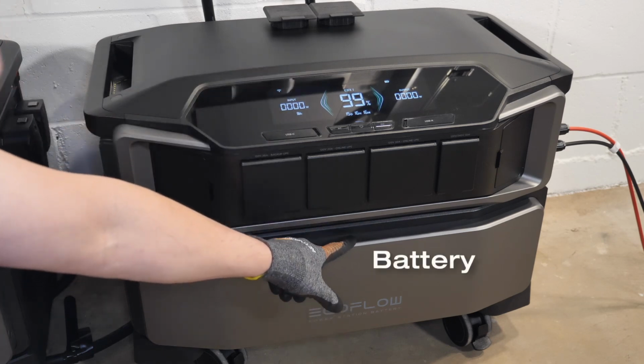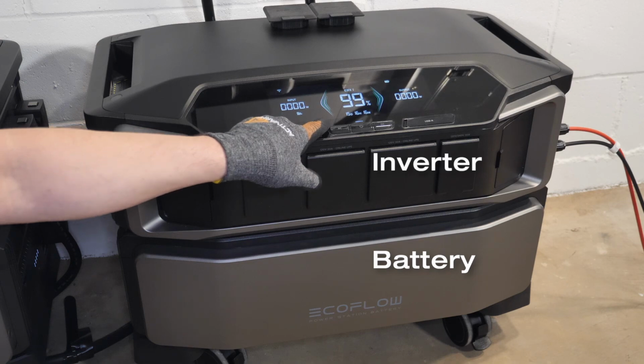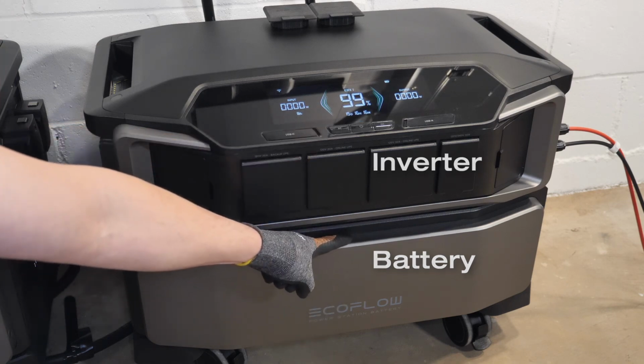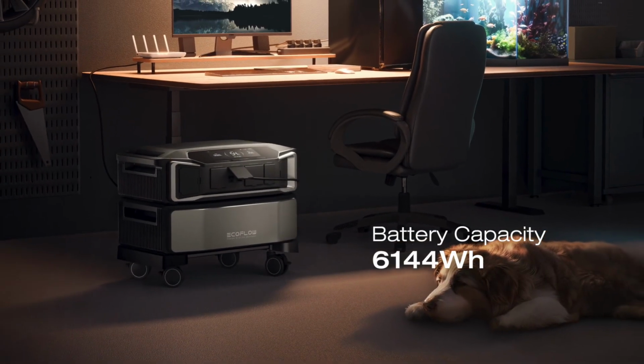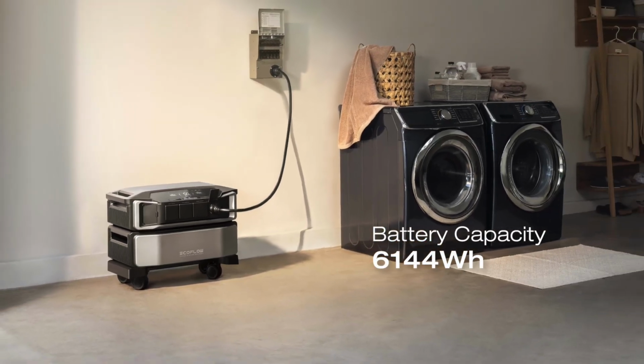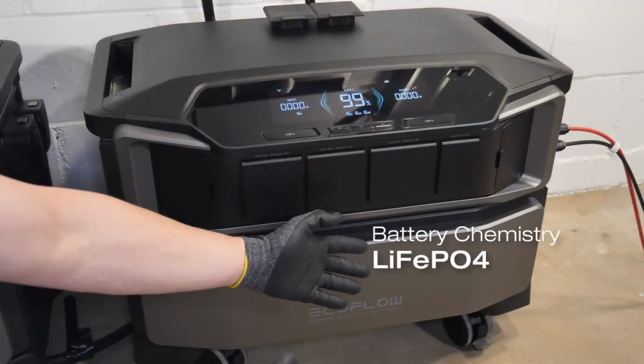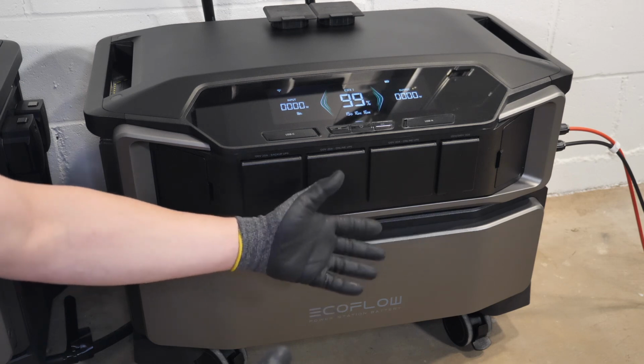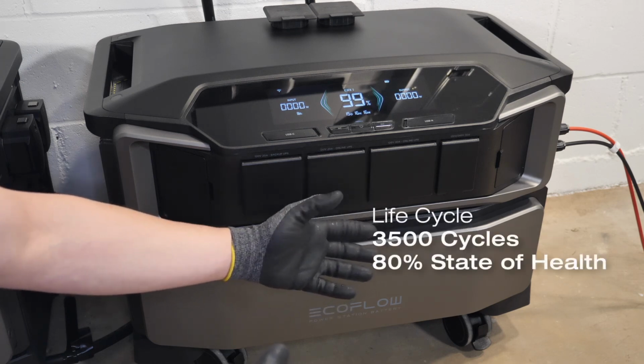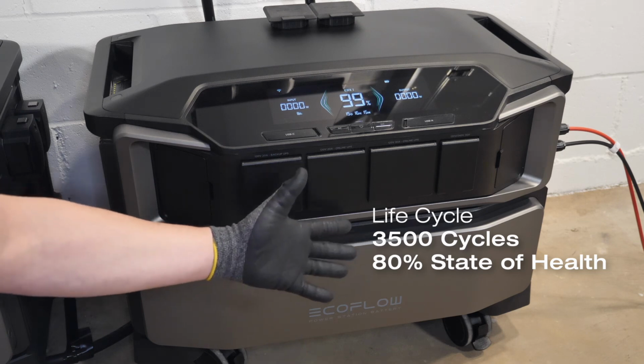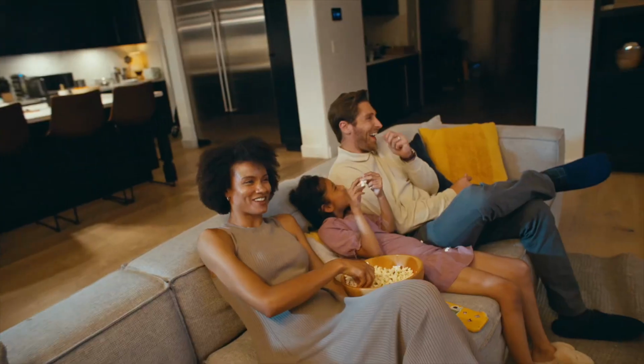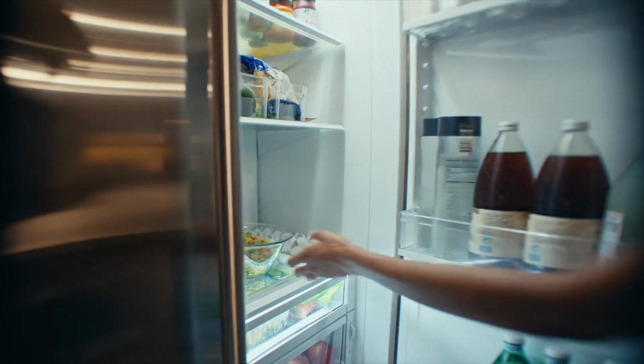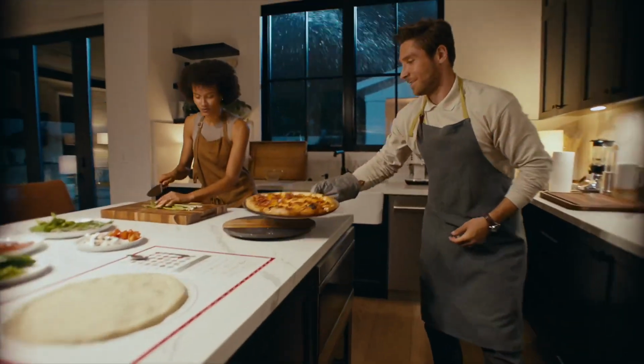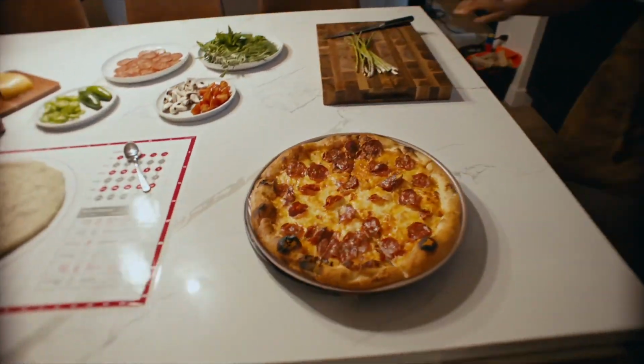Bottom side is your battery and the top side is the inverter. Battery capacity down here is 6,144 watt hours, or 6.1 kilowatt hours. Batteries inside are lithium iron phosphate, with an average life cycle of 3,500 cycles to 80% state of health. That means after completing 3,500 cycles, which will technically take forever, you'll still have 80% of your battery life left. It won't be dead or anything like that, it'll still be usable.